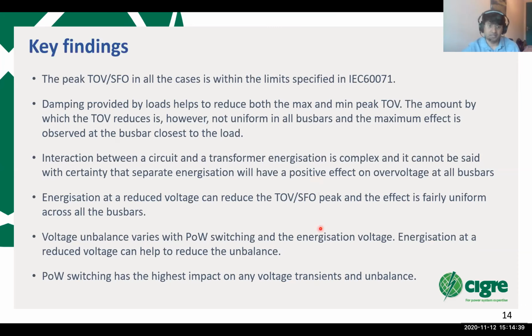But for the energization voltage, we found that it has a uniform impact across all the bus bars, and it helps to reduce the peak TOV and SFO. So this can surely be used as a method for reducing voltage stresses on the network. And for the live trial a couple of weeks back, we actually had to adopt this method to reduce the overvoltages and avoid tripping the generator on overvoltage.